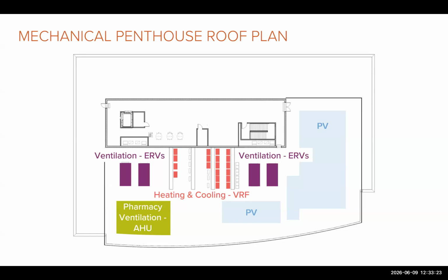The green equipment was a surprise system that we had to add for the compounding pharmacy. This is a dedicated air handling unit which provides both the space conditioning and the ventilation to the compounding pharmacy. The reason we found out about it sort of late in the design had to do with those two different timelines that Lauren talked about. So it really is not ideal to have those two different timelines, and it's something that you have to work through carefully.